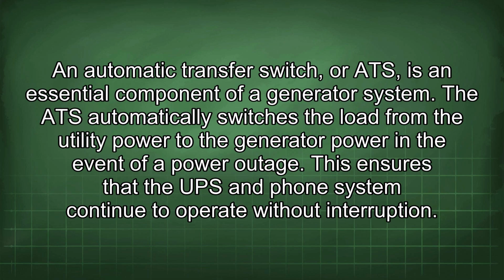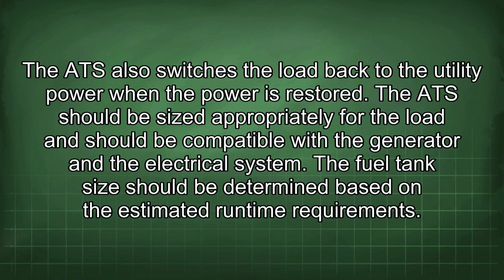An automatic transfer switch, or ATS, is an essential component of a generator system. The ATS automatically switches the load from the utility power to the generator power in the event of a power outage. This ensures that the UPS and phone system continue to operate without interruption. The ATS also switches the load back to the utility power when the power is restored. The ATS should be sized appropriately for the load and should be compatible with the generator and the electrical system.